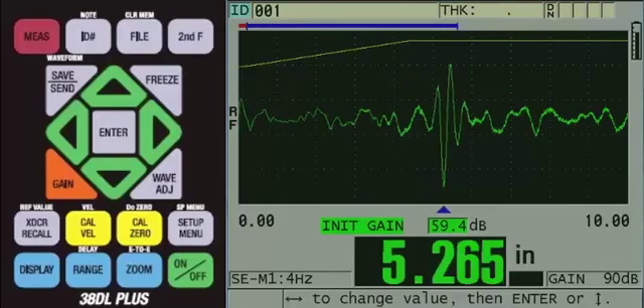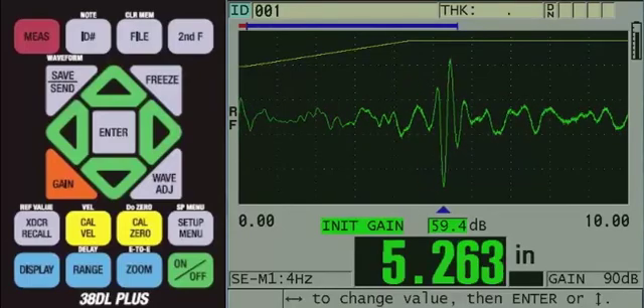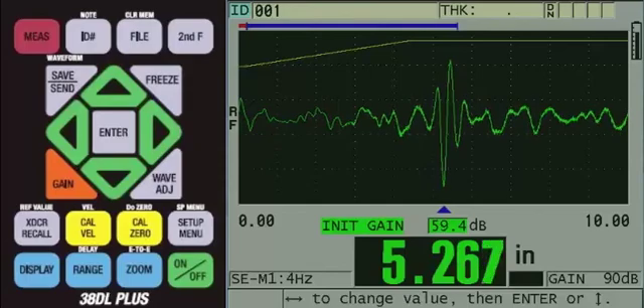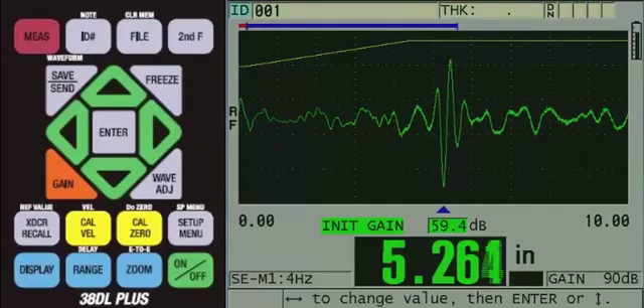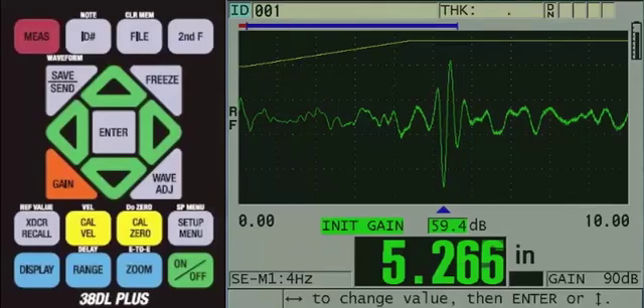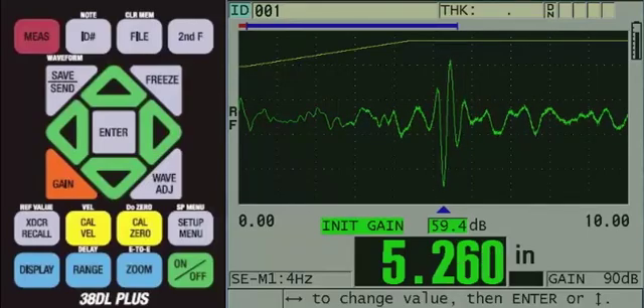Since no further adjustments are needed, we can go ahead and calibrate. For best accuracy, calibrate using two samples of the same material with known thicknesses representing the minimum and maximum thickness.